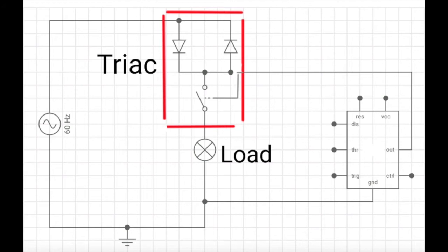You notice how the microprocessor DC ground is connected to the neutral AC line, and that is one of the things that's a little different about a triac versus, let's say, your relay that's only going to have the primary side and the secondary side. They're going to be completely independent of each other, or isolated from each other. And on a triac, they're not.